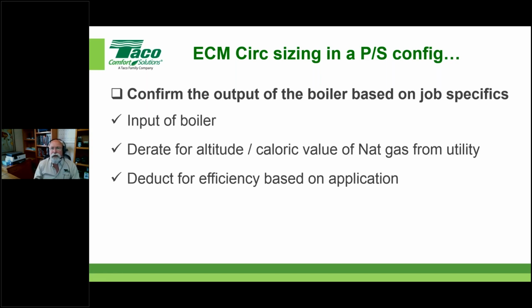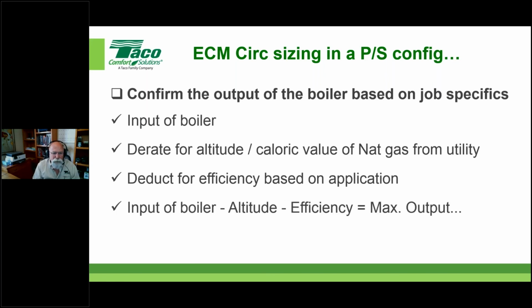Deduct for efficiencies based on the application. That just means, what am I doing with this? Is this going to be low temperature, always condensing? Then you could use your AFUE number. If not, use something less. For instance, AFUEs of 95, 96 — if you know it's going to condense most of the time, use that number in your sizing. But if you're doing a lot of snow and ice melting at high temperature, or domestic hot water generation at high temperature, where return temperatures won't be as low as on a high mass radiant application, don't use the AFUE. Use something less, probably in the neighborhood of 86, just over the edge of non-condensing. So, the input of the boiler minus the altitude derate minus the efficiency will get you to the maximum output of the boiler, and you can size the pump on that.